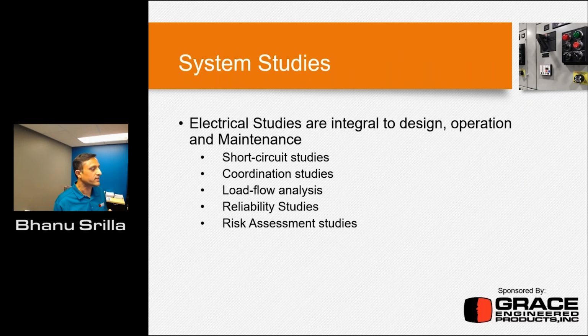System studies are all important things. Electrical studies are integral to design, operation, and maintenance. As I mentioned before, on your single line diagrams, you need to make sure the short circuit studies are done on a regular basis, along with coordination studies, load flow analysis, reliability studies, and risk assessment studies as well. Load flow studies show the direction and the amount of power flowing from available sources to the load, and short circuit or fault currents represent a significant amount of energy that can be released into electrical systems. Make sure that you do the studies on a regular basis.